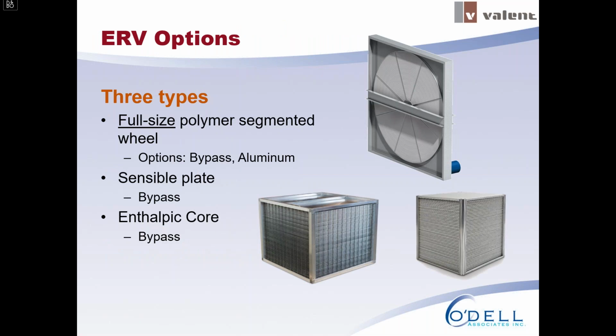Now, speaking about energy recovery, the ERV options available in the standard offering for Valent include a polymer segmented wheel, which is a pretty typical wheel in the marketplace. We do have options of putting a bypass on that wheel, as well as providing an aluminum wheel rather than a polymer wheel. They also do sensible plates, which is an aluminum plate for just sensible heat recovery. That sensible plate is actually built within the Valent plant and is vertically integrated within their building. So it's a great solution for especially areas where obviously you want sensible only recovery, but also areas that are a little bit dirty, maybe plants that you didn't think were great fits for energy recovery. It's a good solution for that.